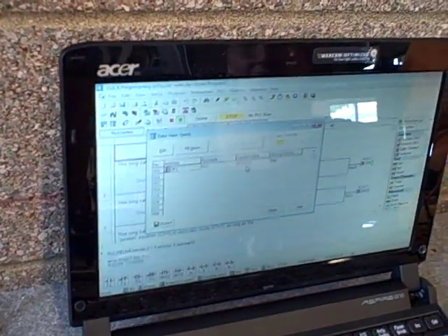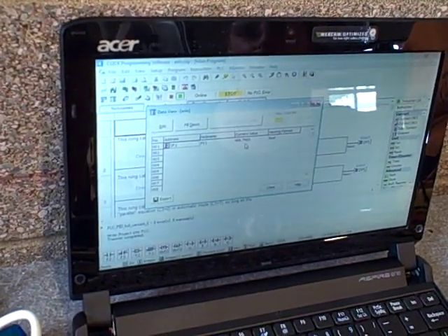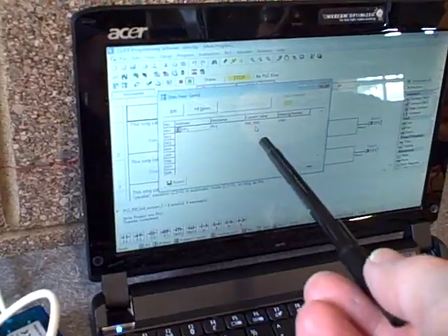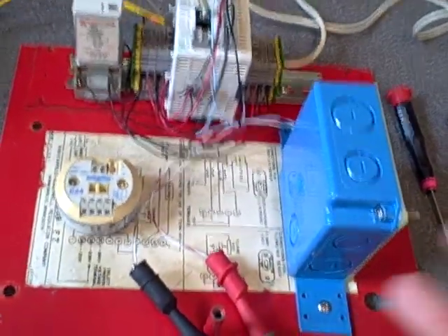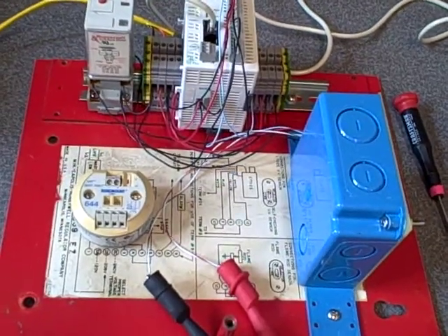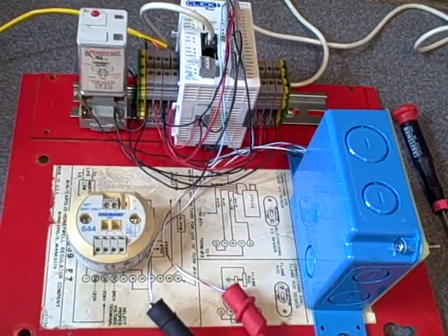And actually, come to think of it, this is a good application of critical thinking when it comes to calibration. We're reading a tad low on the high end. Now, based on the function of this thing, what is it we're hoping this thing will do? Shut down if it gets too hot. Shut down if it gets too hot, exactly.